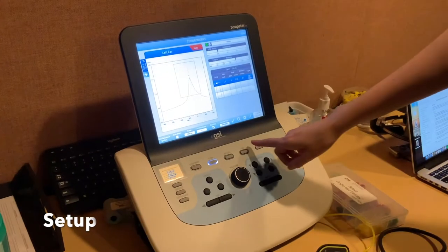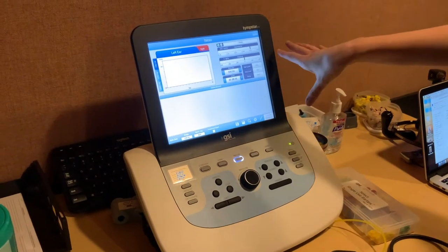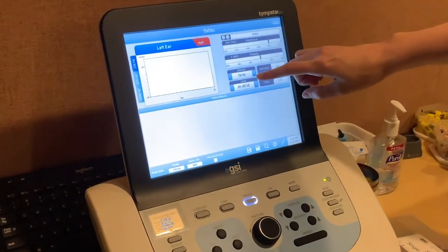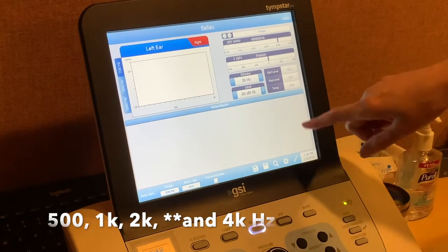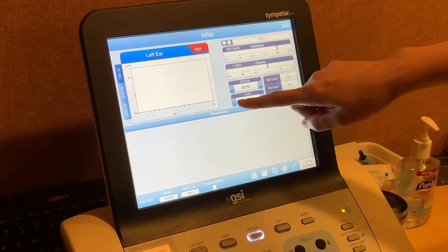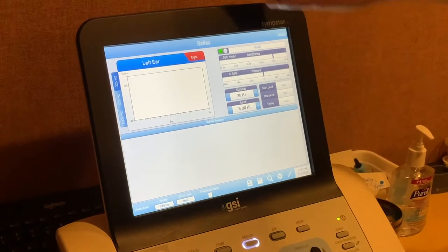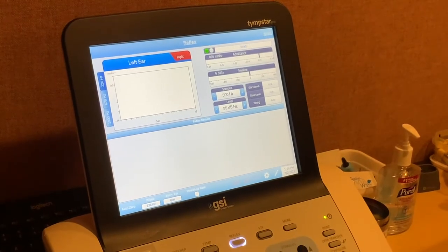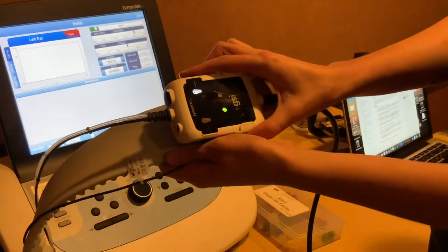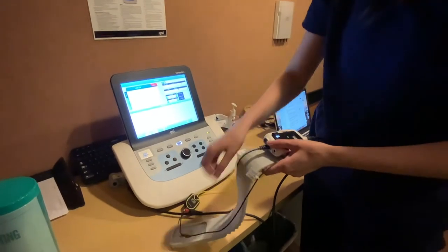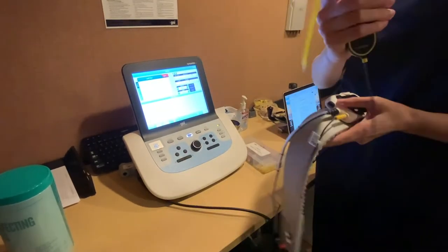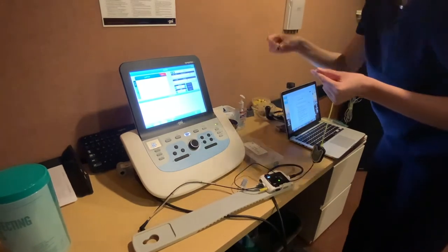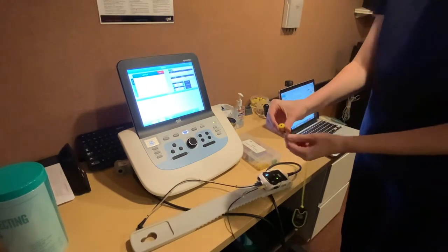So this is how you switch to reflexes. You're going to hit the reflex button and it'll take you right there. Now you can see this is where you can change the stimulus being presented where you can do 500 hertz, 1000 hertz, and 2000 hertz. And then you can also change the presentation level, which right now is set at 85, but we would probably start around 75. And then here again, you can change the ears, right or left. And that would also be changed on the same machine that was used for tympanometry. So right now this is only set up for ipsilateral. To do contralateral, you would need to put this extra probe tip in right here and you can choose the bigger ones, which you'll mostly be using.